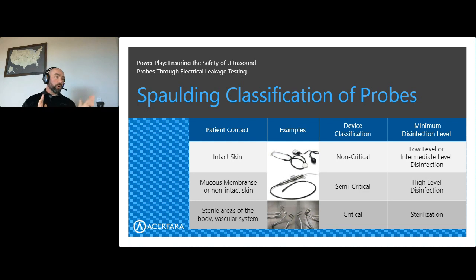The mucous membrane or non-intact skin is classified as semi-critical, and so those require high-level disinfection. Now, all of those endocavity probes are supposed to be in a condom before they're used. And that should prevent, that's our belt and suspenders. That should help to keep those probes from being damaged and to help prevent cross-contamination. Even doing all of those things, we still do high-level disinfection on those probes. Again, those are the longer probes characterized by the long shaft and the tightly curved array at the end. These are endocavity probes, and those are high-level disinfected. TEE probes are in exactly the same category because they're going into the esophagus. Typically, you don't put any sort of cover on those when they're inserted into the patient. And those require high-level disinfection by approved methods.